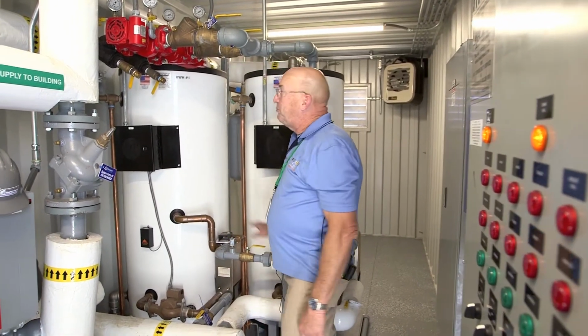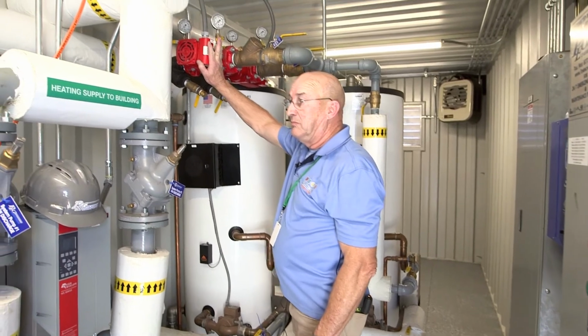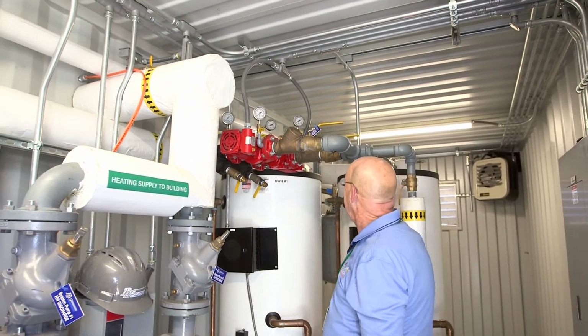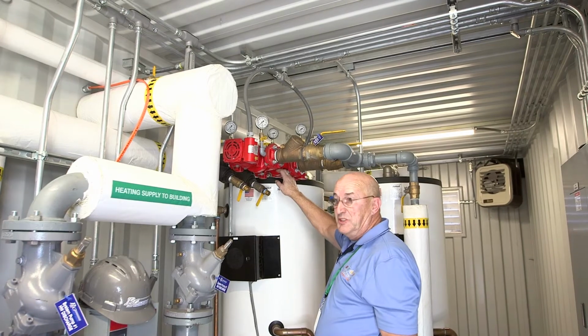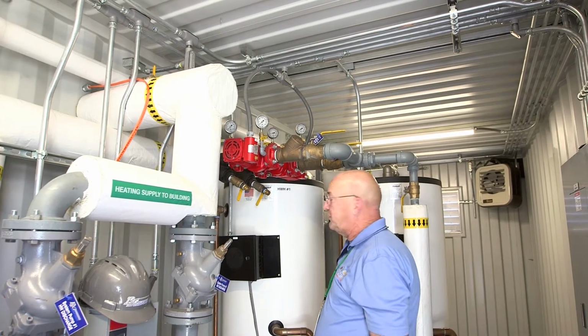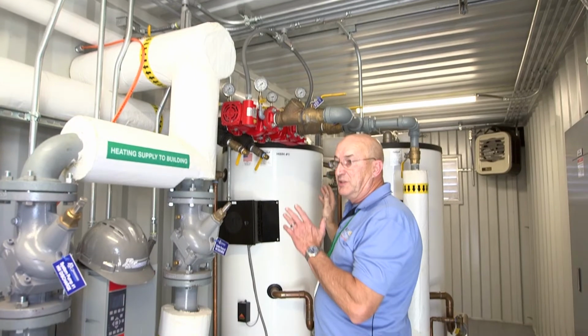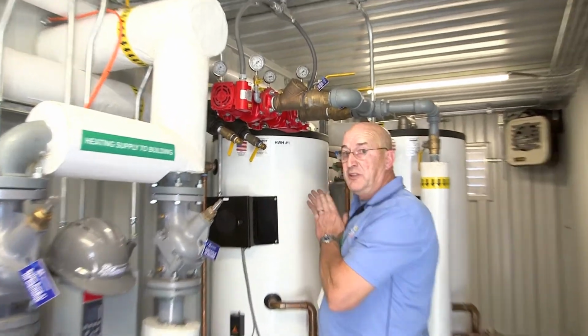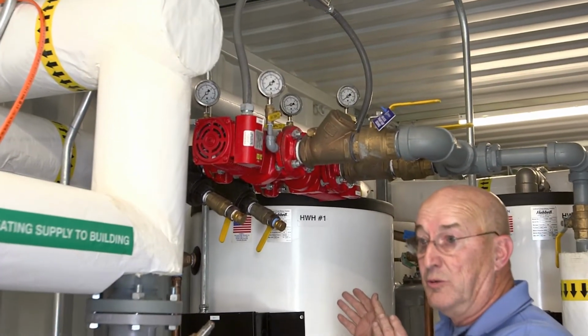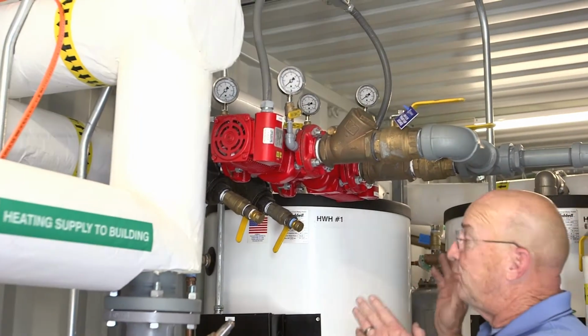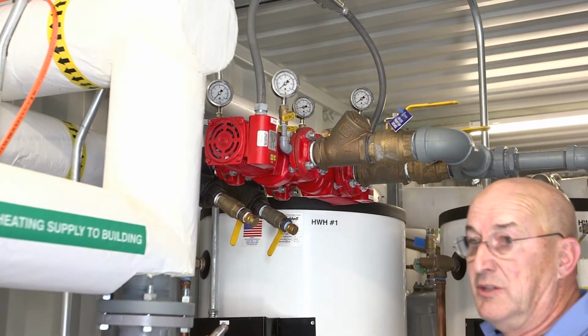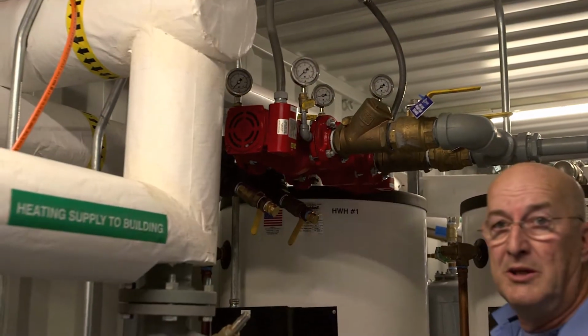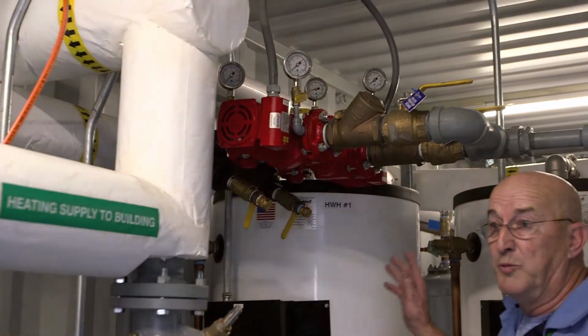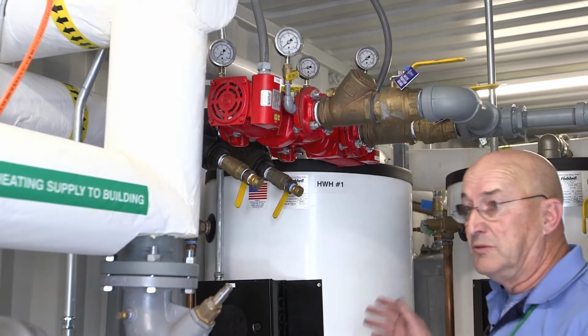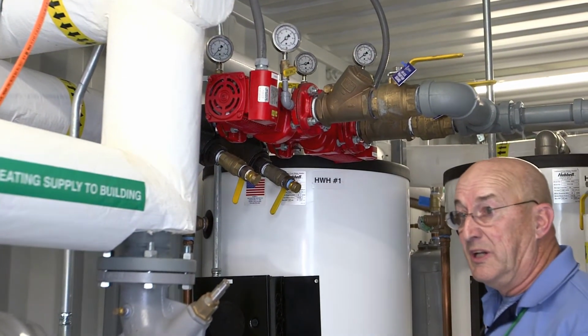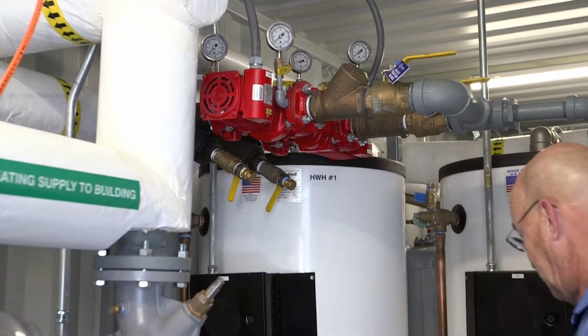So at that point, this pump is for tank number 1. This is a backup. They both work to control both tanks. There's a sequencer so that if one pump fails, it'll automatically switch over to the other so you don't lose hot water. And they'll rotate every 96 hours, so you get equal run time on both pumps. You're not overheating your pumps or putting excessive wear on one pump and not the other. All for the efficiency of it.